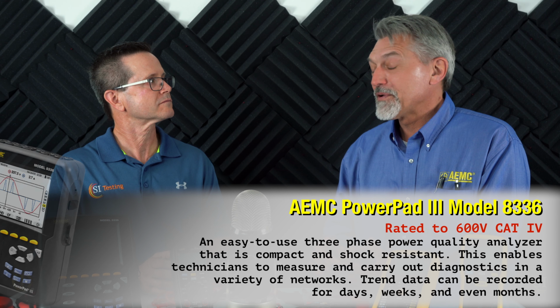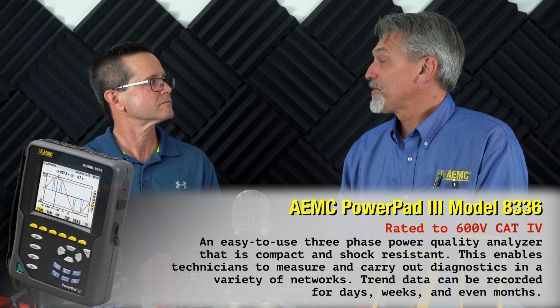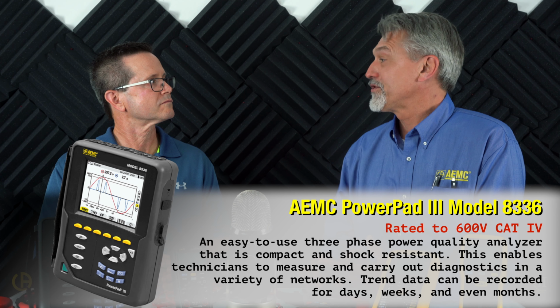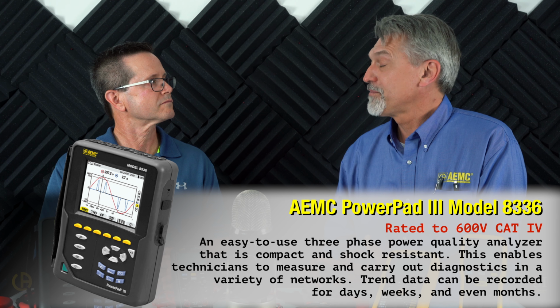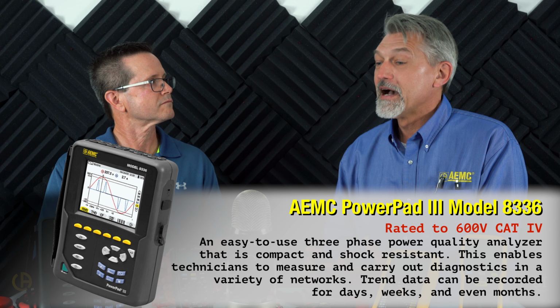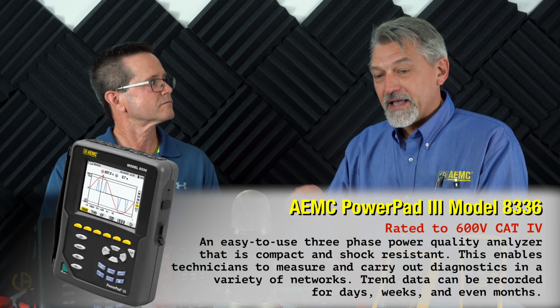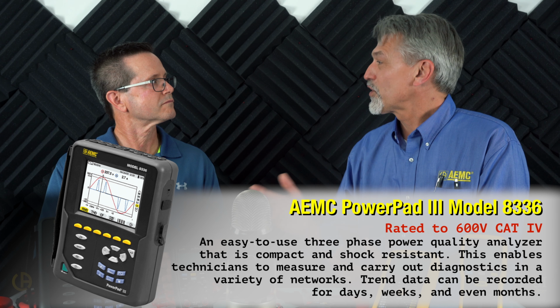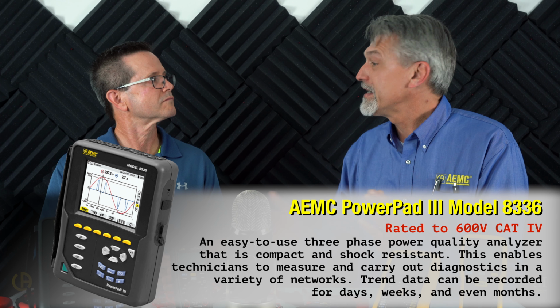So you may want to have a power quality analyzer to do a couple of things. Probably one of the most common uses today is energy surveys. There are a couple of reasons you would do an energy survey. If you're going to add to the energy service in your facility, the electric code says you have to do a 30-day study. So it's really common for us to use a power quality analyzer, because it's a recording device, to do that 30-day study.